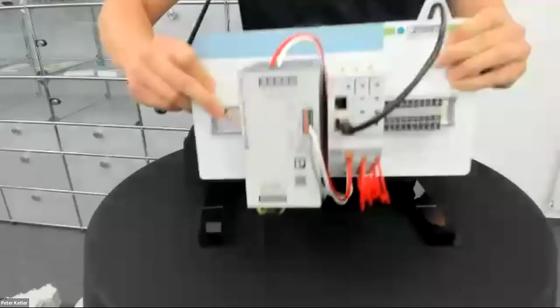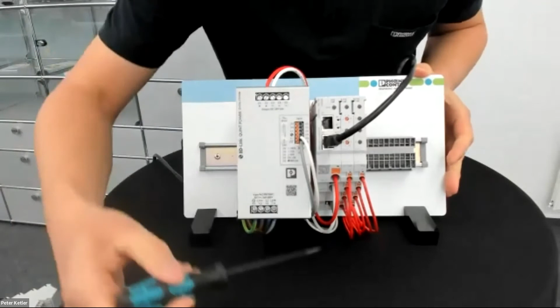All right. So of course, we also can have a look at the CAPAROC as well. It looks quite similar. So here you see a small mock-up. So in this case, the power supply is also provided with 3 phases, 20 amp going out there and 24 volts. It will be delivered here down in the head station, here where also the Ethernet cable is attached. And as Peter explained, this is now transmission to each circuit breaker module. And in order to establish a data connection, these 2 wires are connected down here to the terminal block. These wires are standard wires on both setups, so you don't need a special wire to establish a data connection. Then on the front, we have 2 Ethernet ports you can use for daisy chaining your Ethernet system in order to get the data from the PLC.